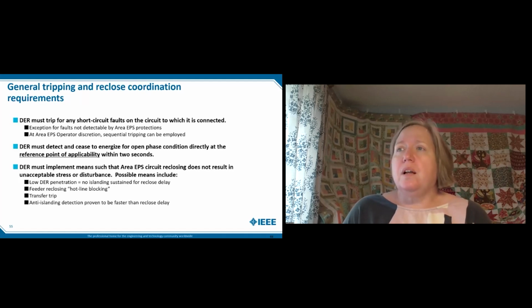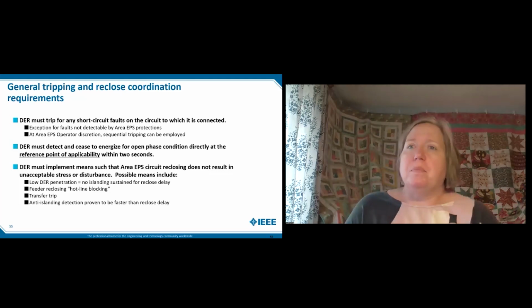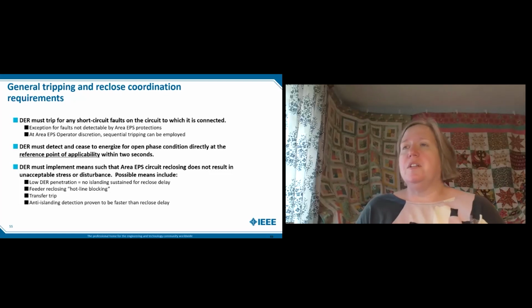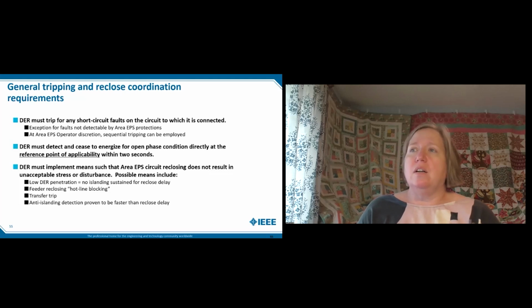So the reclosing against DER is always a bit of a battle. There are decisions the Area EPS has to make with the DER on the system. If there's low DER penetration, you don't do anything. As your penetration increases, you might install line VT and do some hotline blocking. You might do some transfer trip. You might look at the anti-islanding and see if it's going to operate faster than your open interval on the reclosing. So there are options that the Area EPS can implement to mitigate the impact of DER on its reclosing scheme.